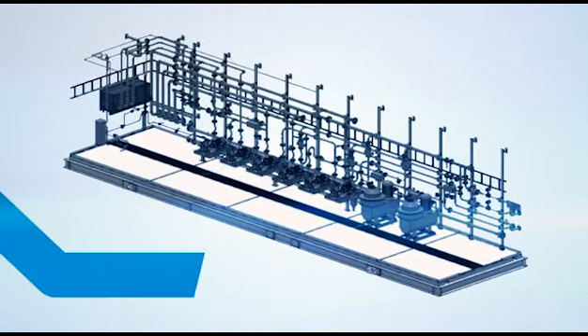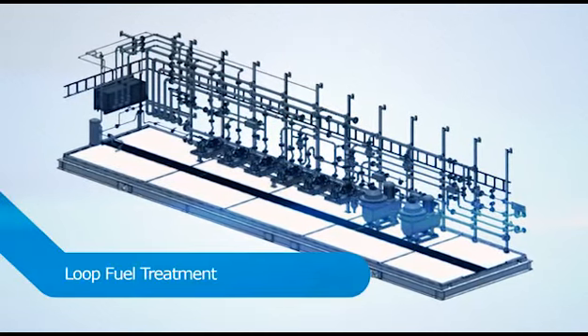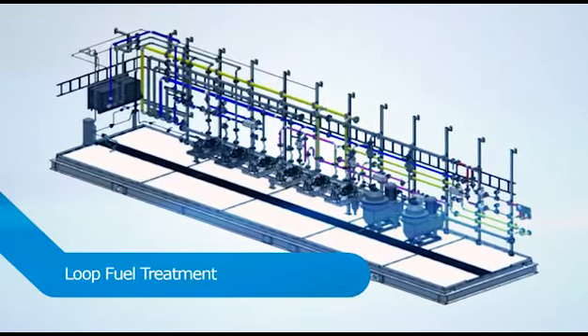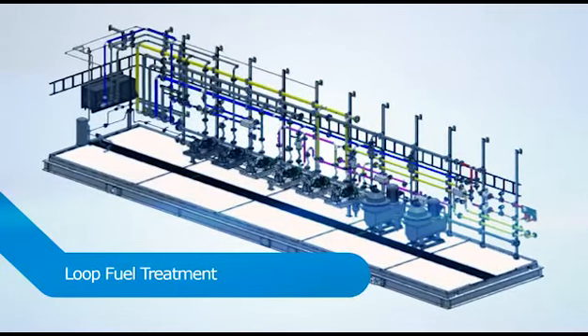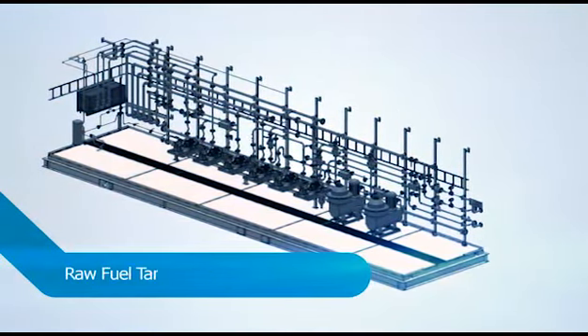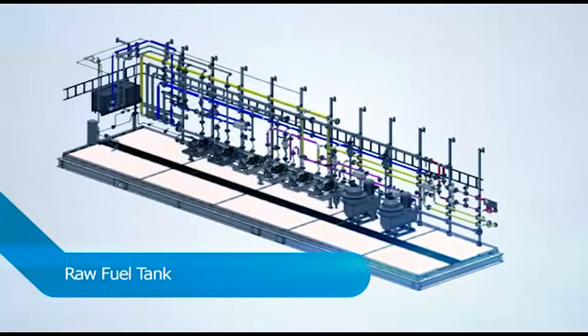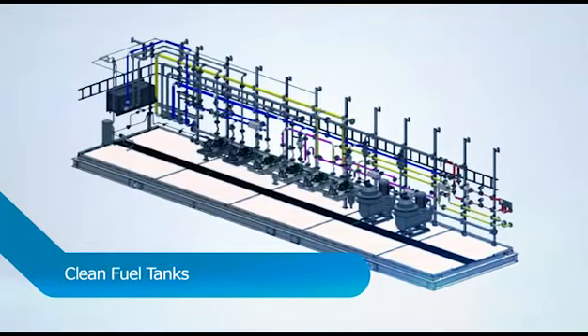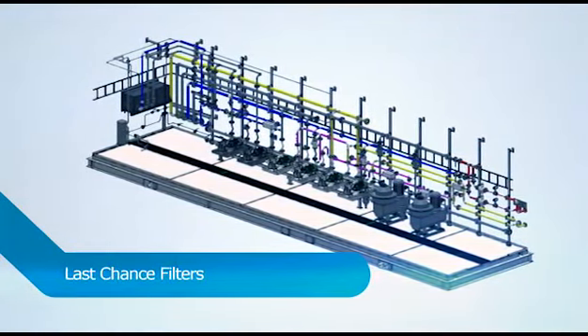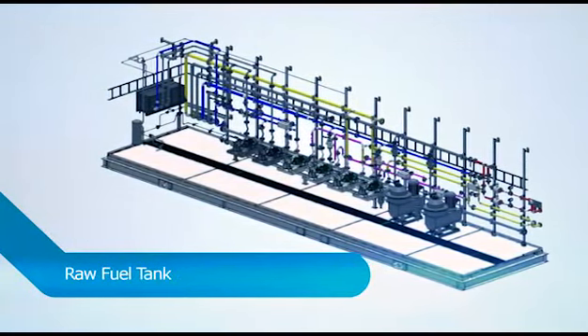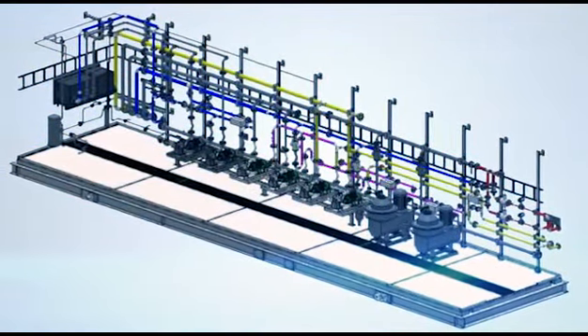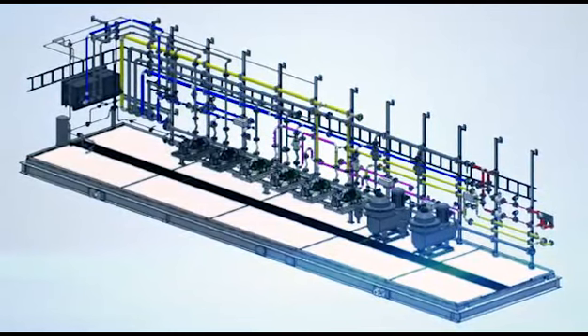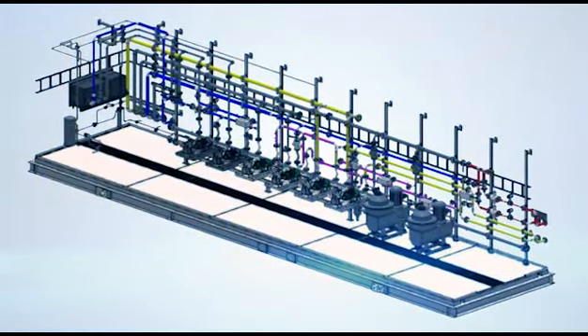A bypass line and valve has been incorporated in the fuel block to facilitate closed-loop fuel treatment and line flushing. When the valve is open, fuel will circulate from the raw fuel tank through the centrifuges to the clean fuel tanks, to the last chance filters and back to the raw fuel tank. Flushing is typically performed after construction completion or as part of operator training.